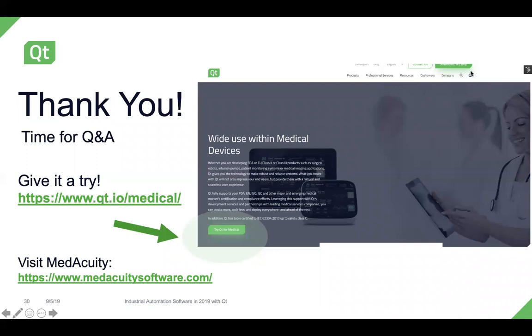I doubt that actually answers the question. It's a difficult question to answer because it's one of those it-depends questions. It will also depend on the safety category of your device and your level of concern for your software. But assuming you're talking about a high level of concern, something like a class C, class 3 device, that's where you do need to have the evidence that your requirements led to your designs, and that's really the definition of traceability. Traceability is the mechanism by which you show that.